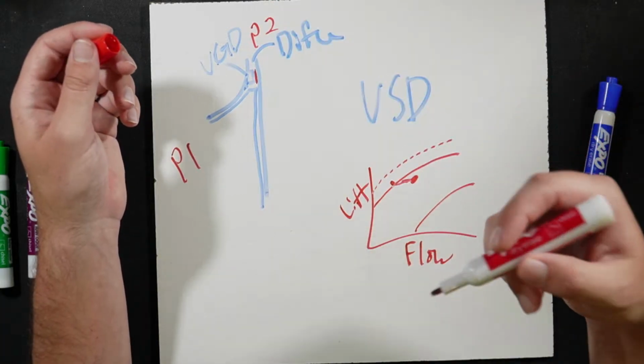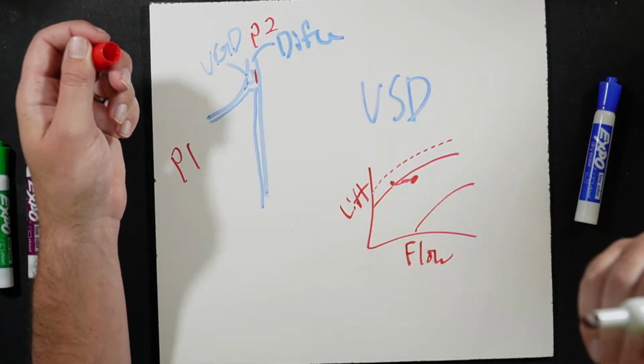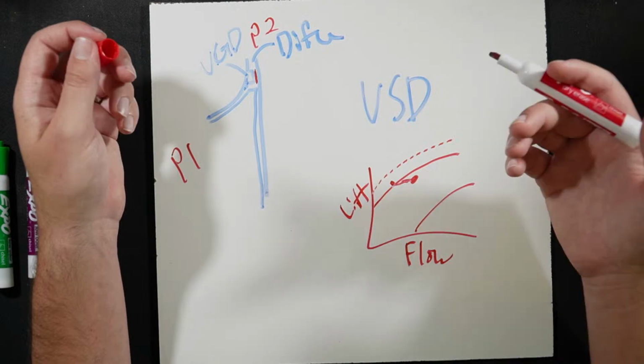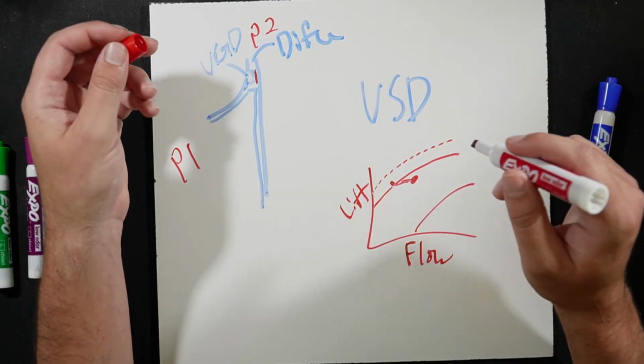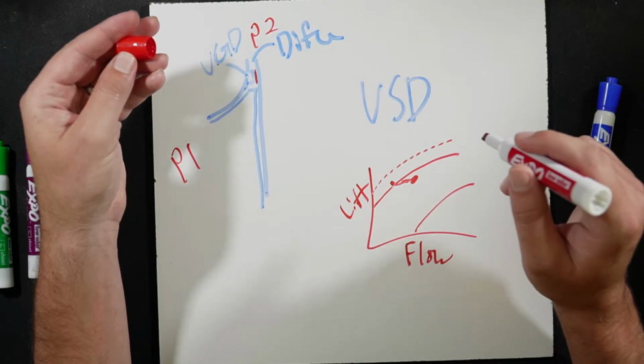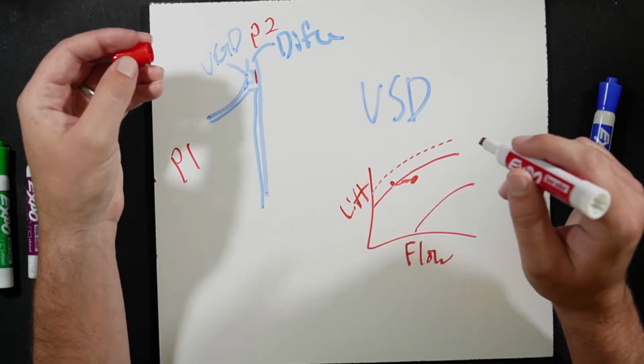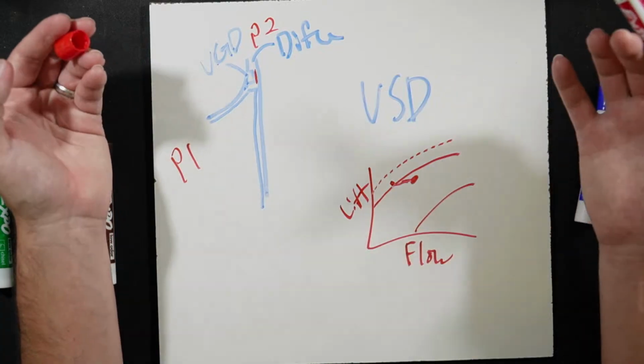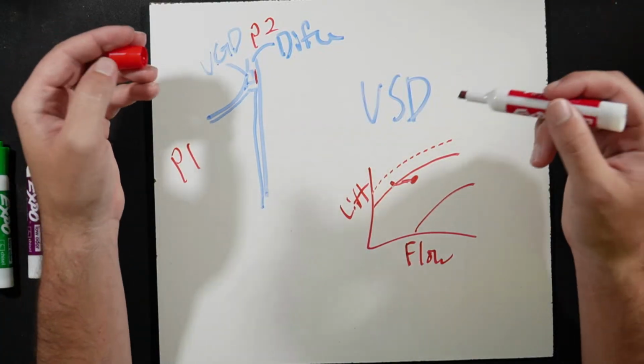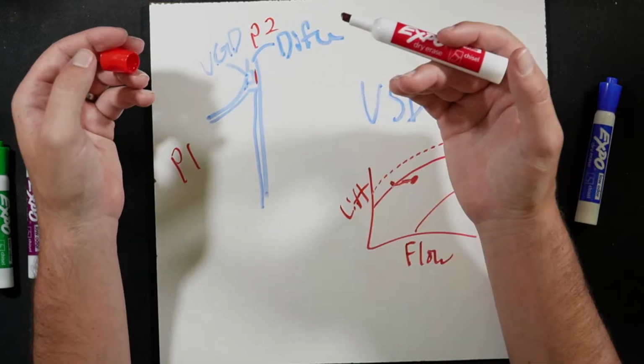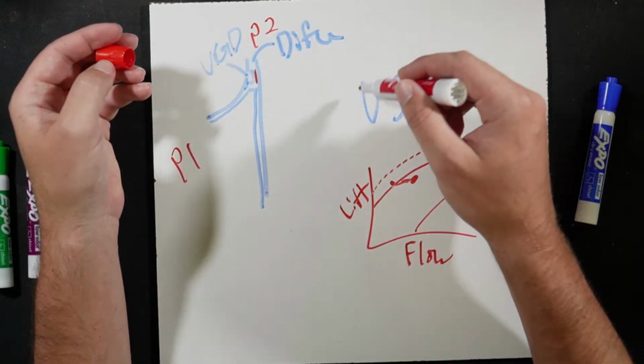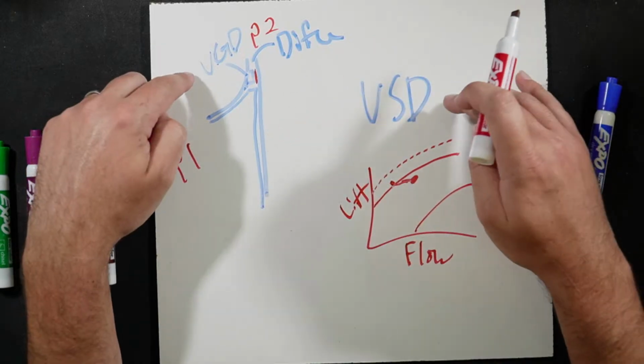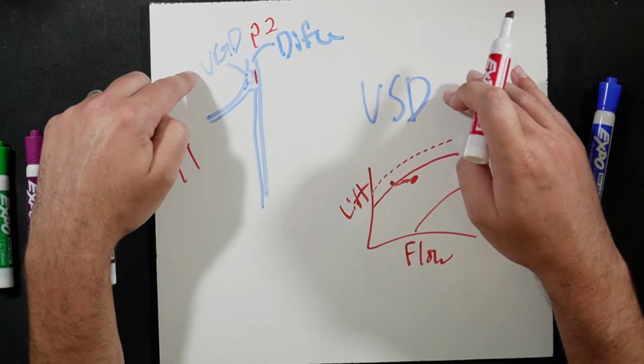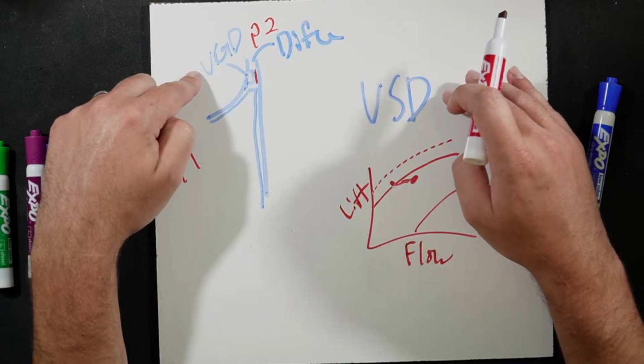even further. So your YMC squared or a YZ for sure works like that. Those do not have an IGV. Yes, and your YMC squareds are also this way. So those are magnetic bearing machines, but those are two examples of where we don't have variable guide vanes coming into the compressor. We just have a VGD and a VSD in order to modulate flow. So they're in part load conditions. It just kind of depends on what they're going to do.